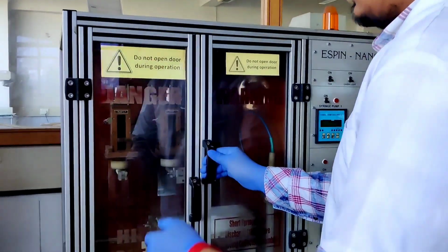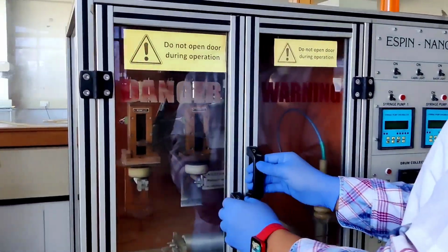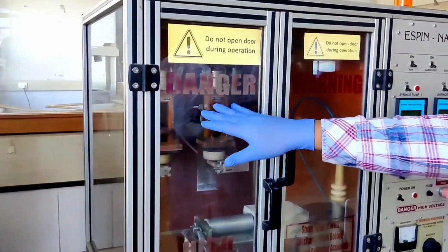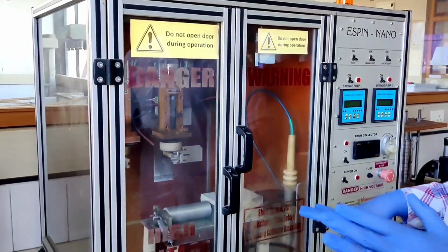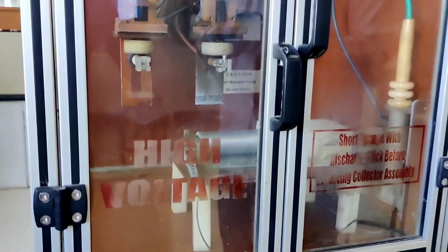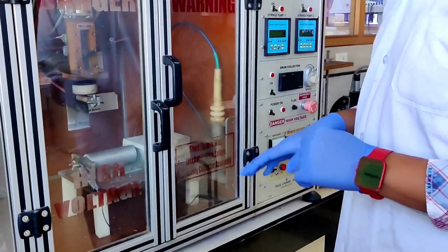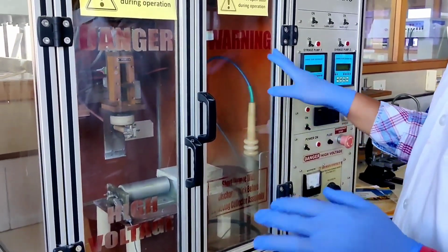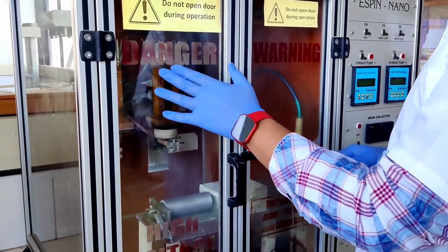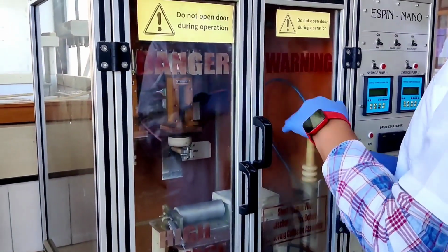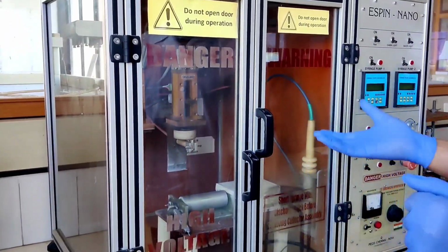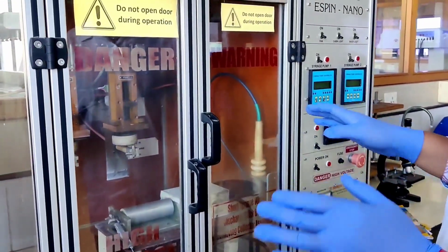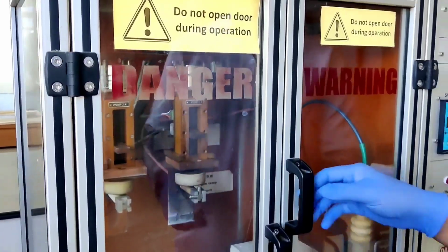Here we can see the door of the chamber. It is denoting that it is dangerous, high voltage. So it is quite risky, due to the high voltage, to open the door during the operation. So take proper precautions. As soon as you open the door, discharge the system using the earthing stick and then move on to the further process. Let's see the assembly.